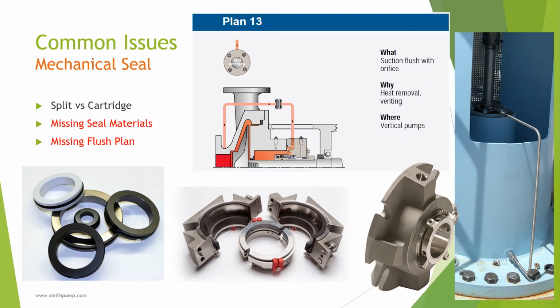And we also always recommend a seal flush plan to be used with the mechanical seals. A plan 13, as shown on the far right, is typically used on vertical turbines. This piping plan allows cool water to flow past the seal faces and carry away heat. The heated water is returned back to the suction barrel for repumping.